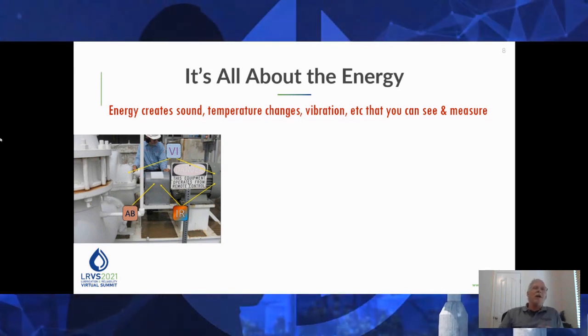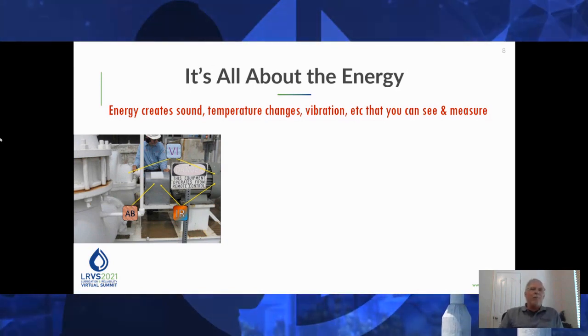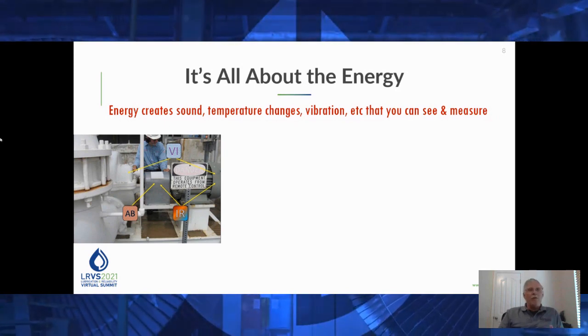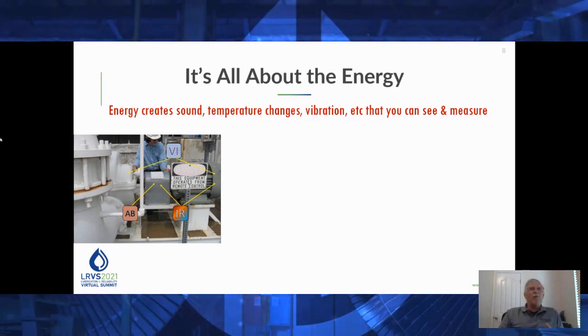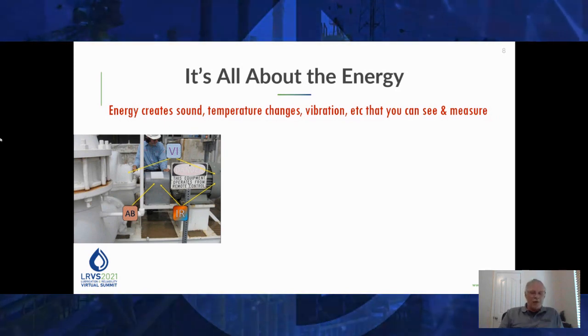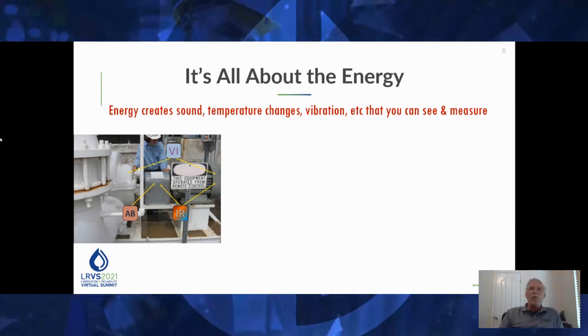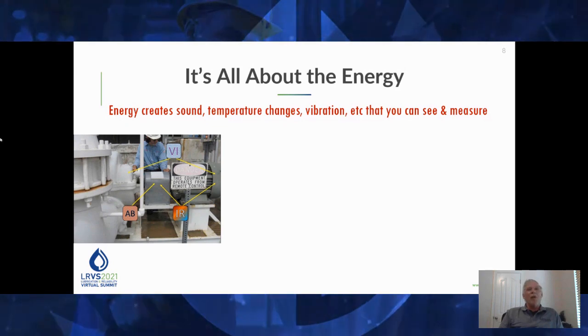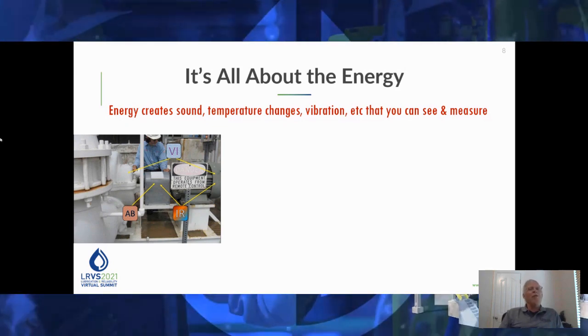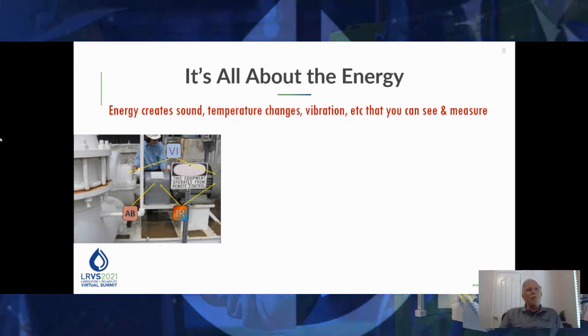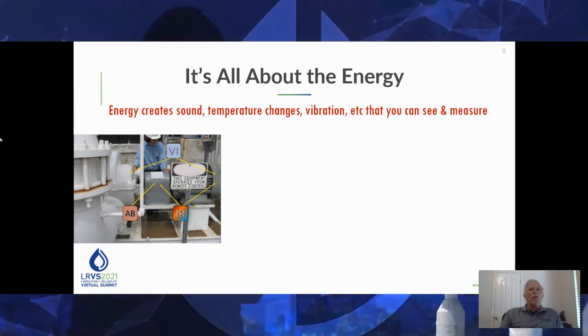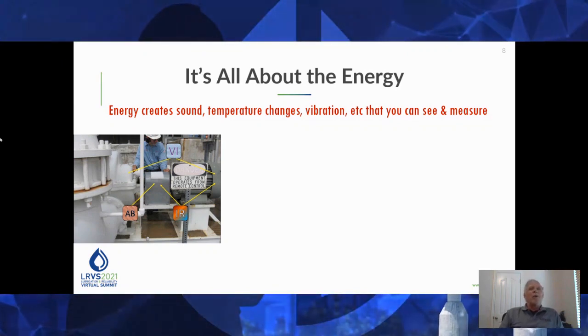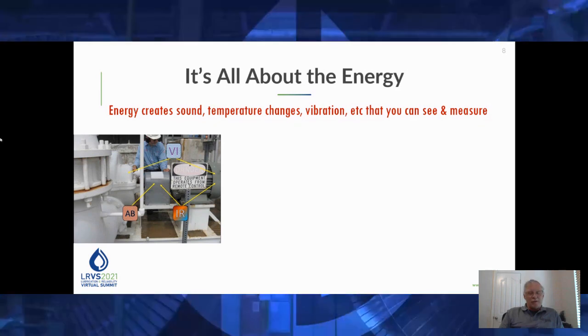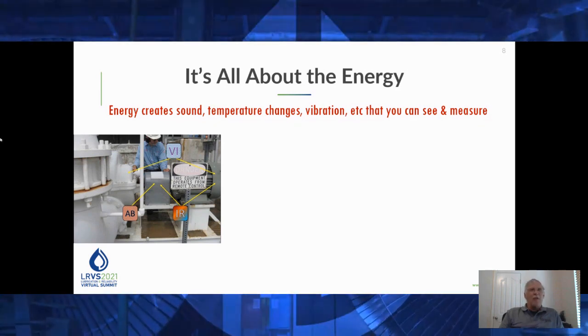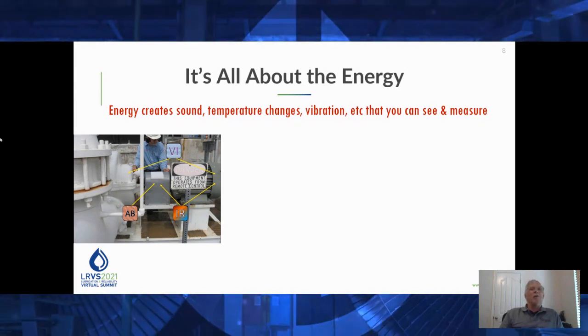I've got vibration I can do on the pump. The vibration can tell me a lot of things, right? If I'm doing vibrations on the pump, then I've got vane pass frequencies, I've got possibly ball bearing frequencies, I've got flow kind of frequencies, I've got balance frequencies, all of those things. Then you've got the alignment of the coupling and the motor and everything.